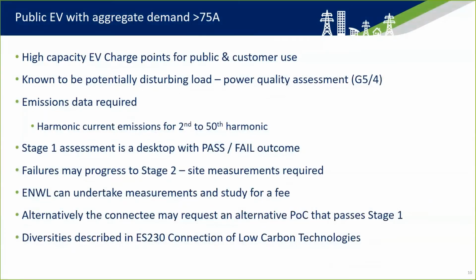So we treat the higher capacity devices, and I'm talking here about devices generally 75 amps or more, public EV charge points, slightly differently, because we do know that from a power quality point of view, they do emit more in terms of harmonic current, so they're more likely to potentially cause disruption to our network. We do have obligations under our distribution code to manage power quality on the network, so when we get new devices connecting which are potentially disturbing loads, we do have to follow a standard process.